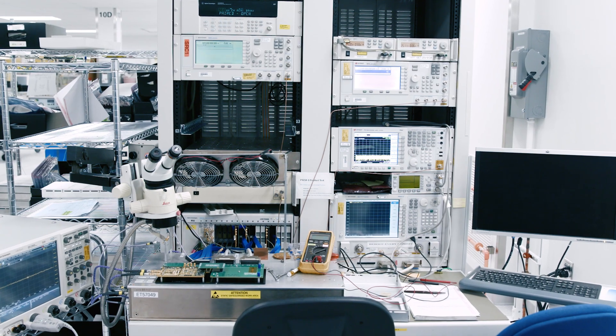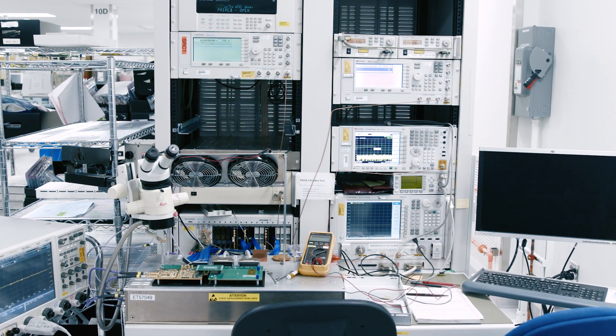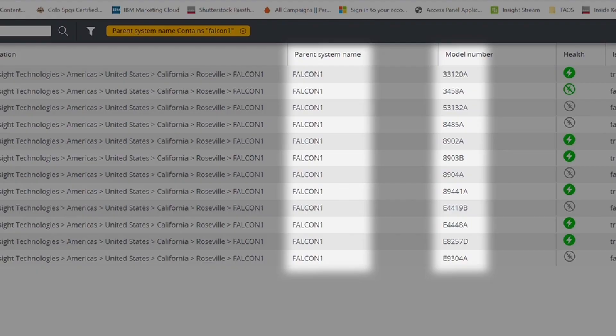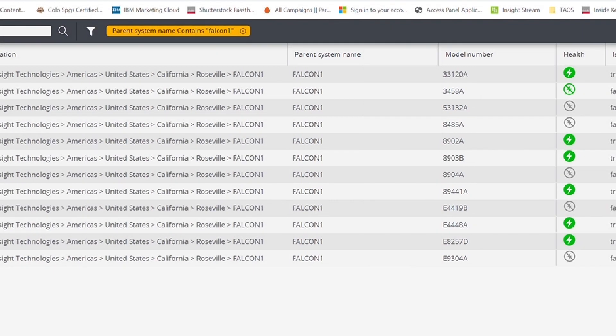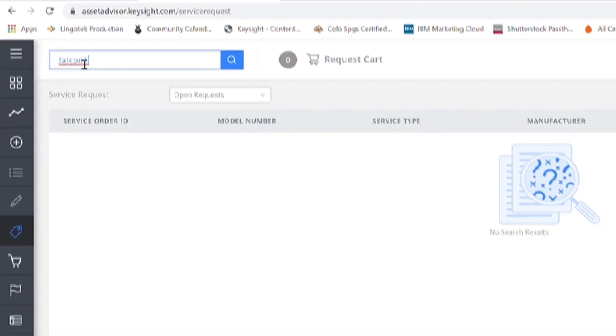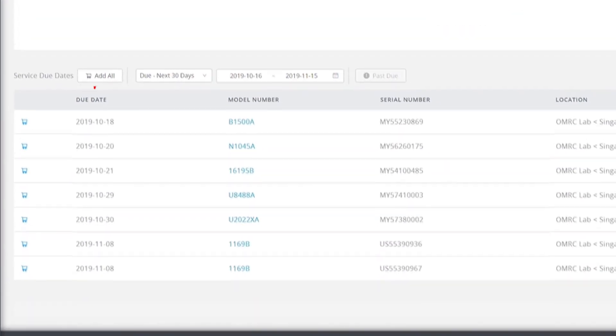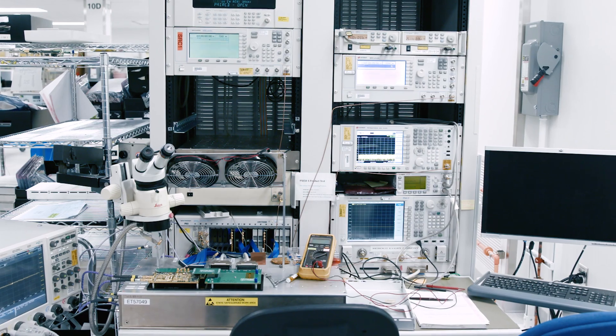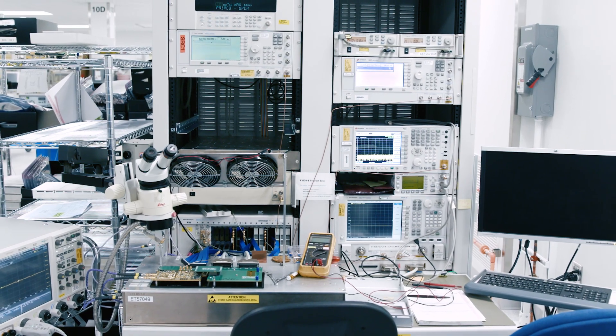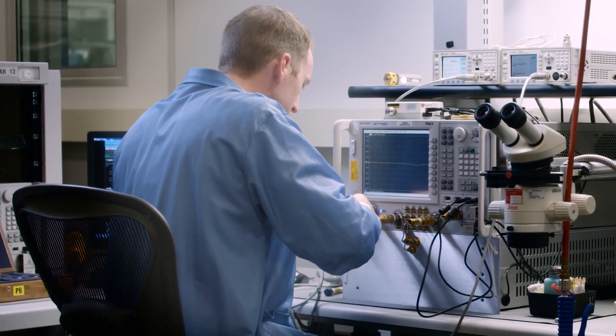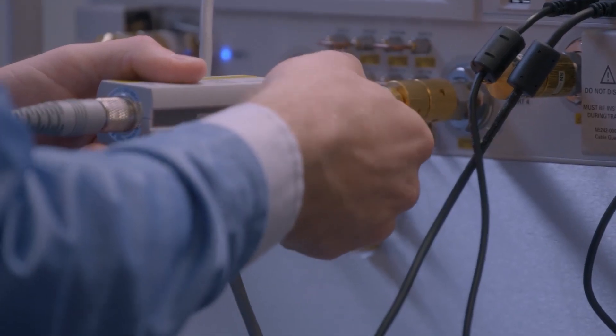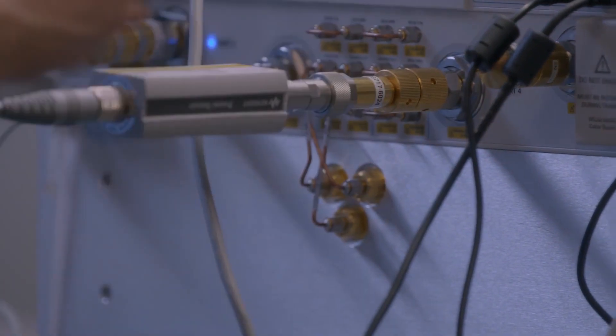For example, a test system comprised of multiple instruments can be calibrated together, avoiding longer-than-needed downtime when calibrated individually on separate due dates. As an example, some instruments have service due dates in October, some in November. With that in mind, you quickly decide to calibrate all your instruments in October, reducing downtime of critical test systems.